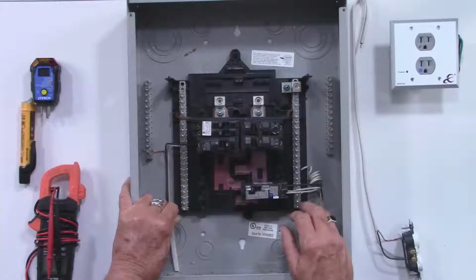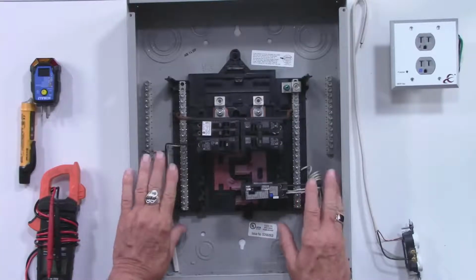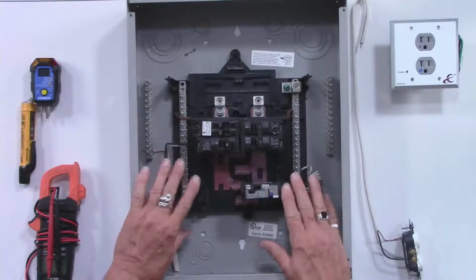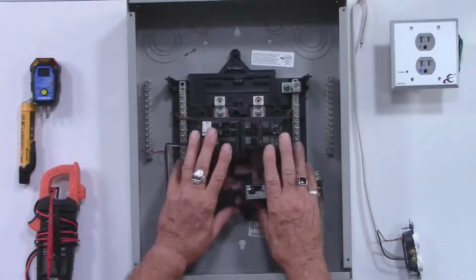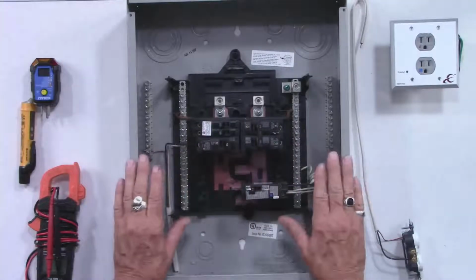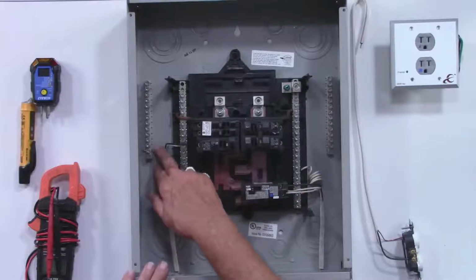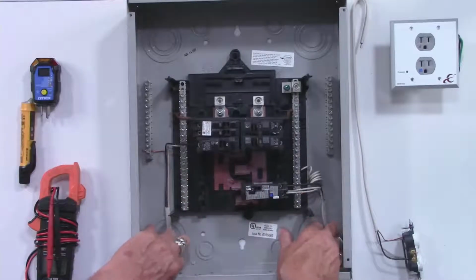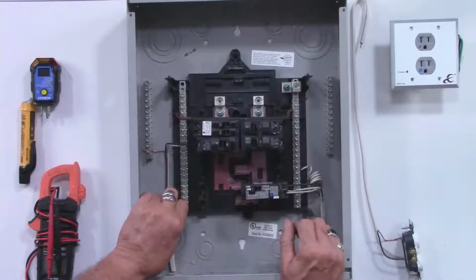That is correct. And then our grounds are separated in this instance. At the first means of disconnect, they will be bonded together. But at the second means of disconnect, separating them eliminates a lot of the noise, and the ground is much for your protection for any kind of shock. For water damage or shocking, stuff like that.